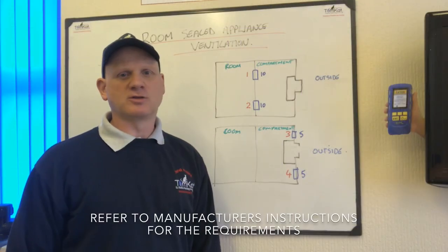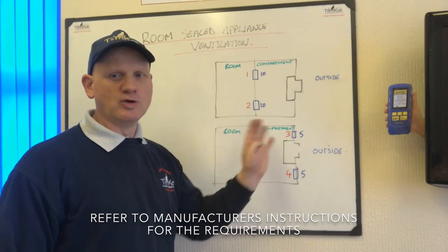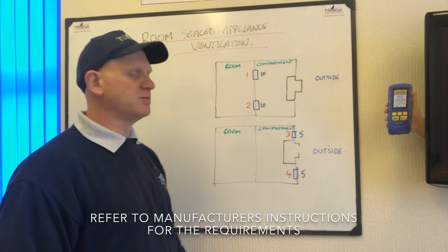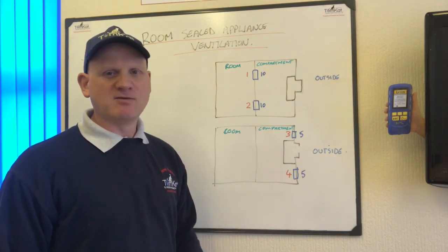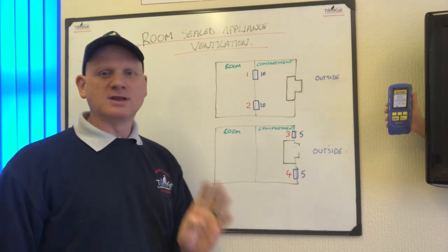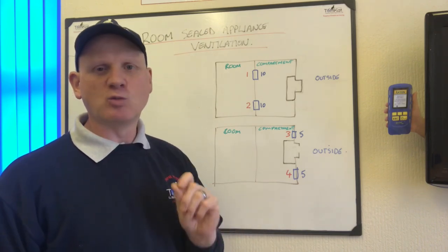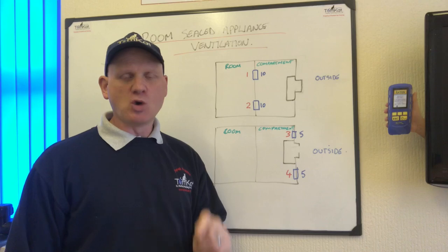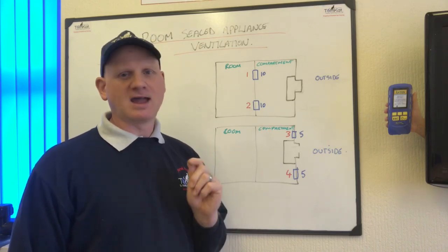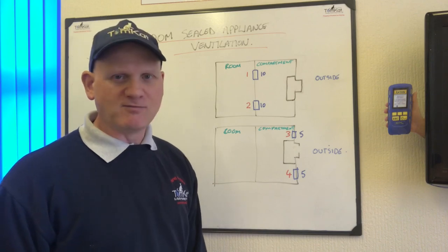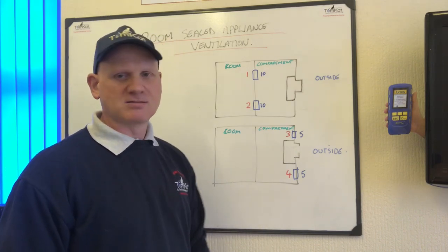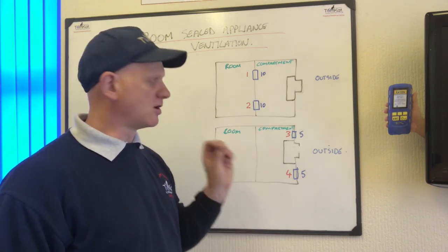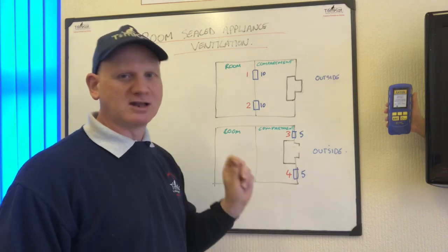The next part we're going to look at is compartment ventilation for room sealed appliances. This is different from open flued because room sealed appliances only need compartment ventilation for cooling, and only if they are high water content cast iron heat exchangers. There are no condensing boilers on the market at the moment that require compartment ventilation for cooling — it's the old balanced flued boilers.